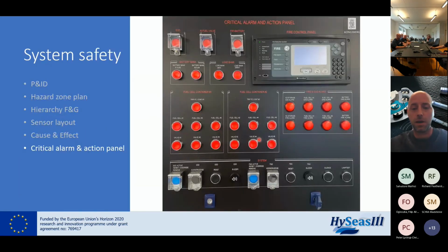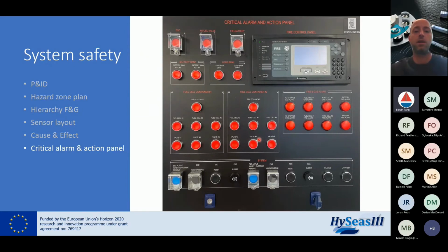I don't have an image of the actual alarm, but it was the gas sensor in the container that went off in the storage container, and that immediately shut down fuel valves. It shut down the ESD valve in the gas container, closes off the load banks, and shuts down batteries, so it leaves the site stopped. That went accordingly, according to the hierarchy and cause and effect that we designed. So that was quite good to see.